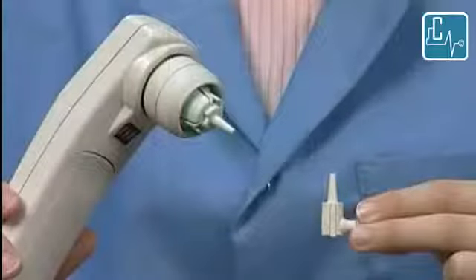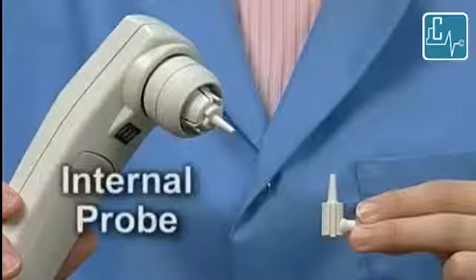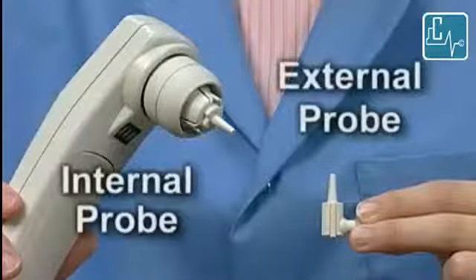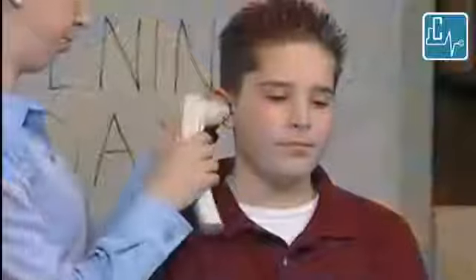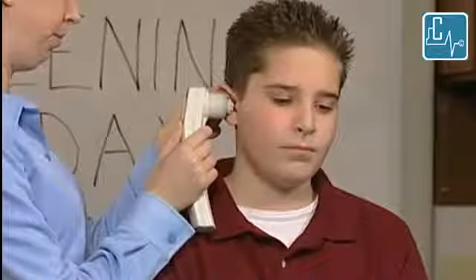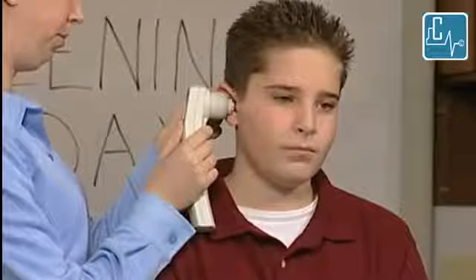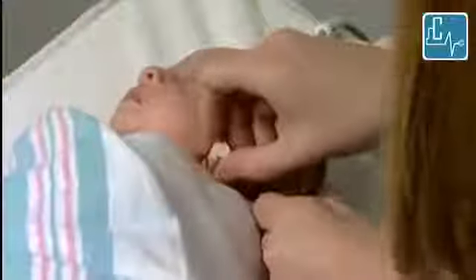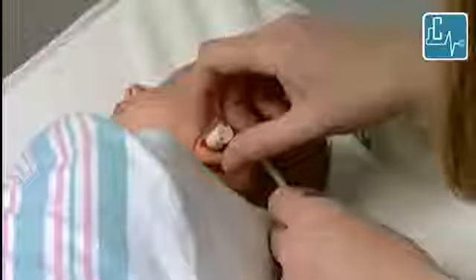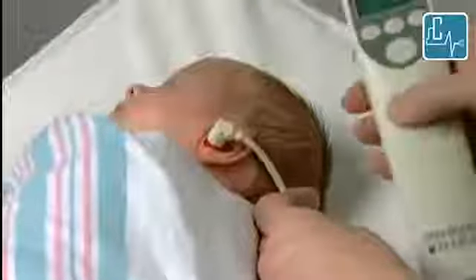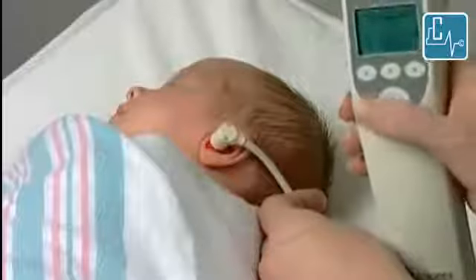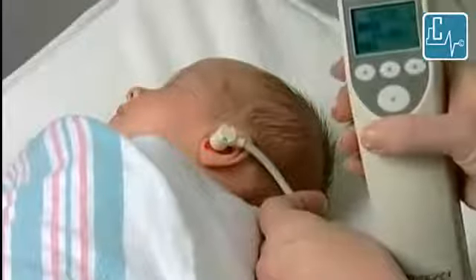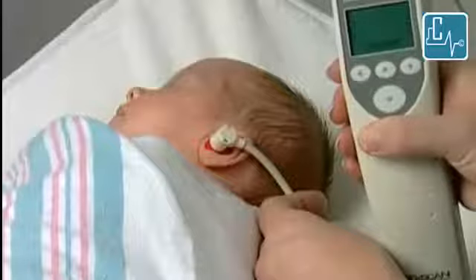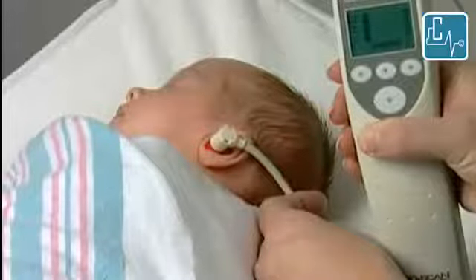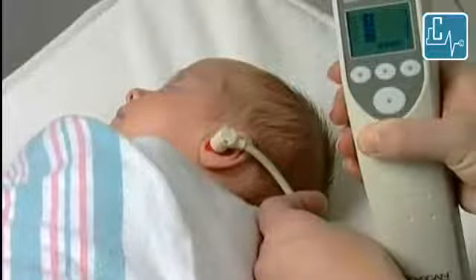Please note that the ERO.SCAN system can be used on all test populations with either the internal or external probe. However, to give you some guidelines, the internal probe is generally used for children and adults, while the external probe is used for newborns and special needs populations. Please remember that these are only guidelines, and you should feel free to use what works best for you. For this demonstration, we'll be using the external probe on a newborn.